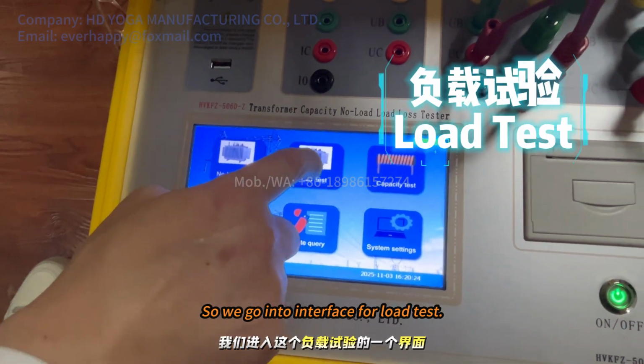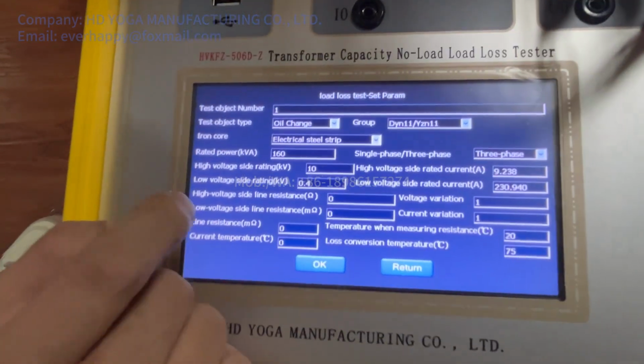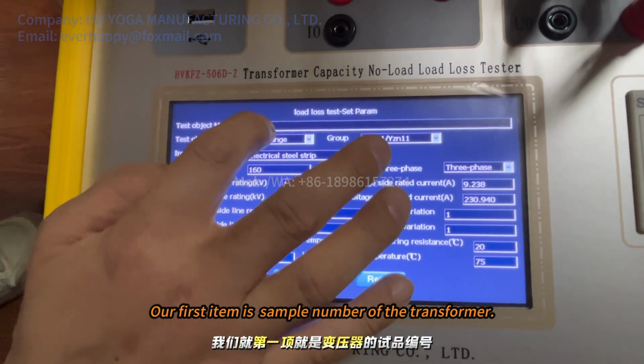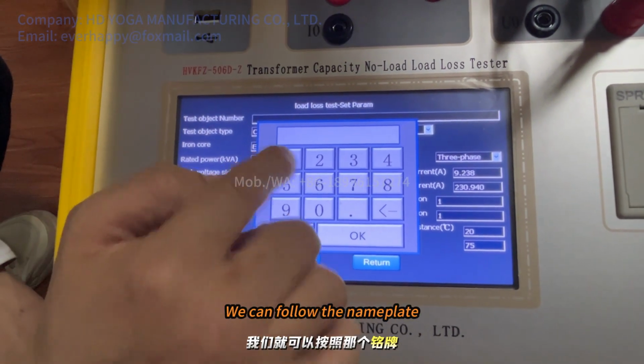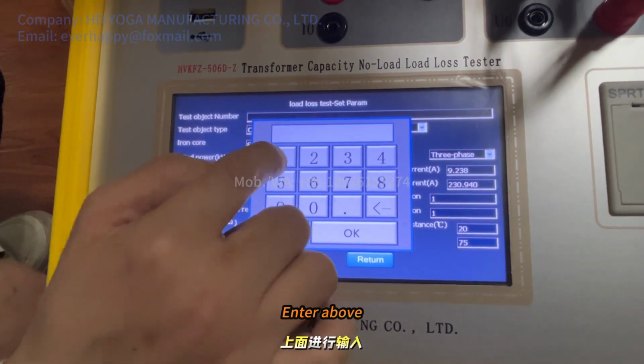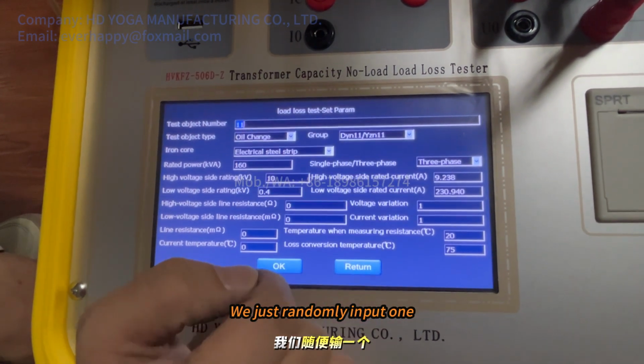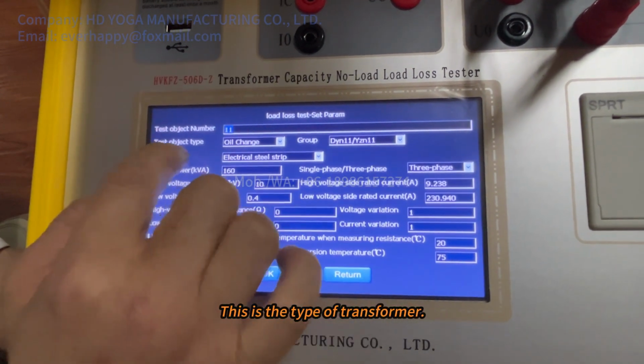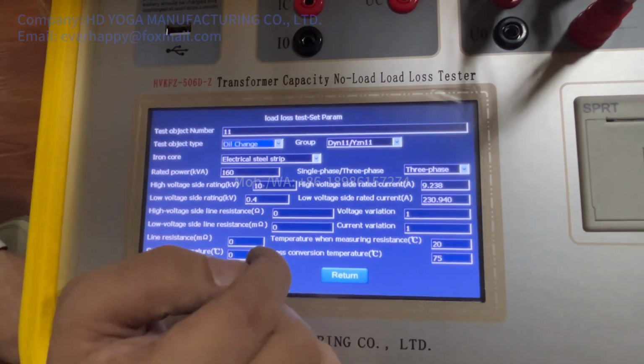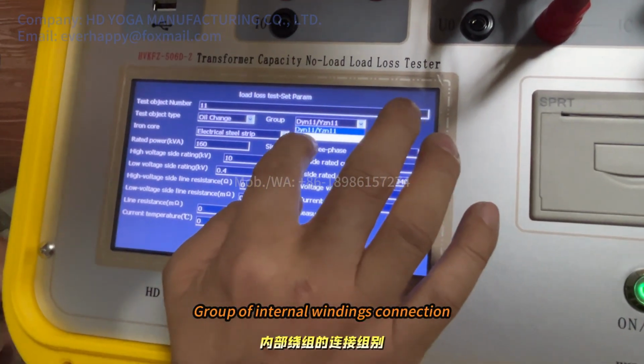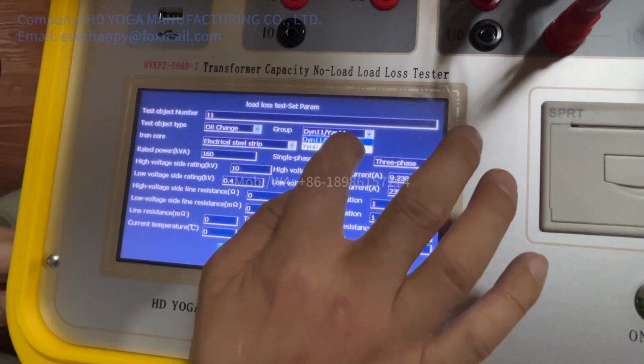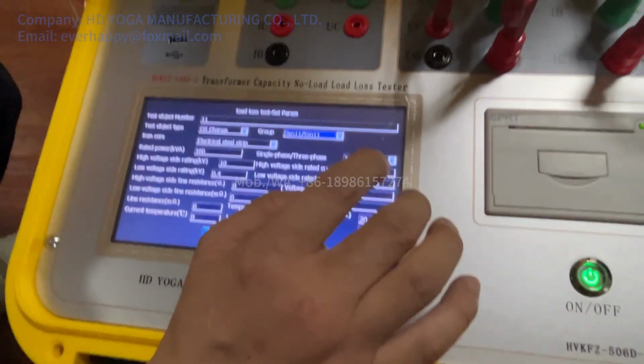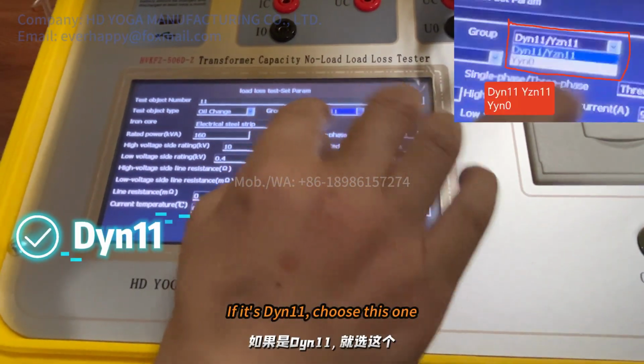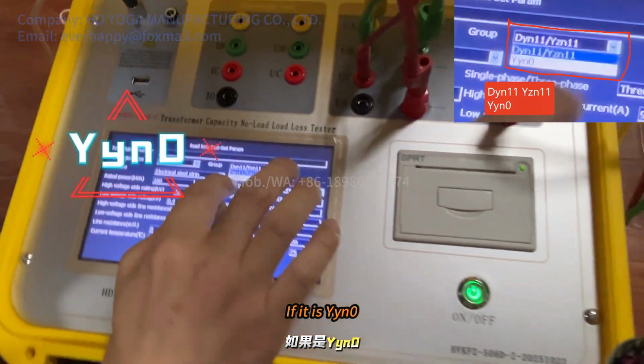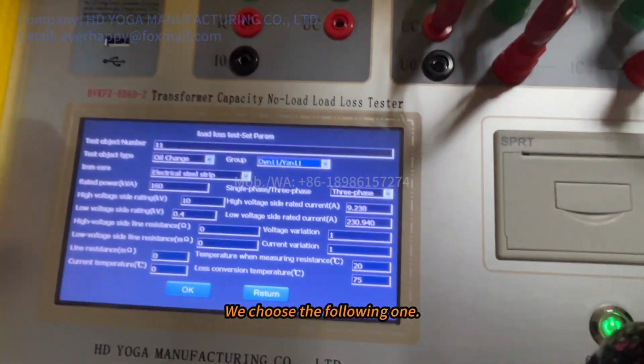So we go into the interface for the load test. Same here, our first item is the sample number of the transformer. We can follow the nameplate. Enter above; we just randomly input one. This is the type of transformer, oil type and dry type. Group of internal windings connection: 2 choices, select according to the nameplate. If it's Dyn11, choose this one. If it is YYN0, we choose the following one.